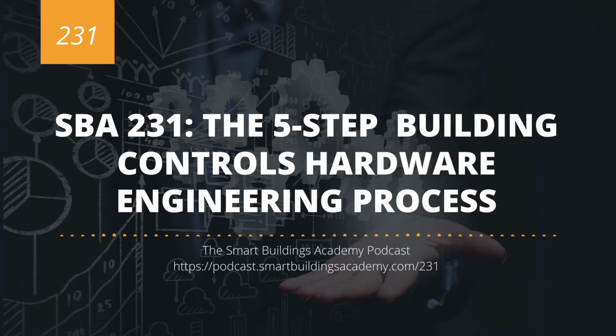So the key focus points I want you to dial in on are, first, the scope review of the scope letter. What you want to understand here is what systems are in scope. And this is going to become very important when we perform our takeoffs, because we're going to align our takeoffs to the in-scope system. So what systems are in scope? What is expected to be done with these systems? Were there any hardware or software promises? Software, however, is going to go more towards the software engineering, but you still need to be cognizant of it. And what timeline was promised, what exclusions, and what assumptions were made.